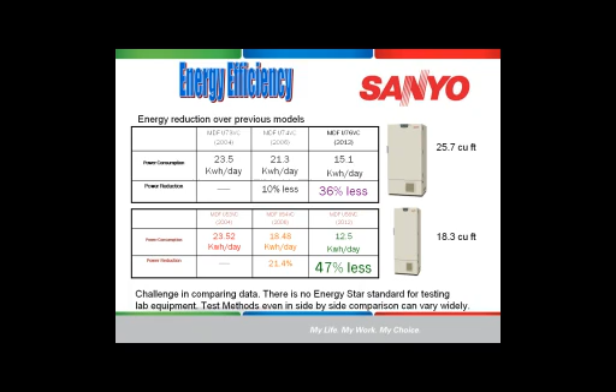Next issue and next thing that customers are looking for, because very often freezers are now stored in customer lab spaces where in the past that wasn't the case. So footprint has become a very important issue for high density storage, is what a lot of us are calling it now, as in how much space does a freezer take up in the room. Most manufacturers are moving toward vacuum insulation panels on the walls. In the past, the average ultra-low freezer, and still the conventional designs of ultra-low freezers, use 5-inch walls. You need 5 inches of blown insulation to be able to get enough R factor to be able to give you enough performance on the freezer so that you wouldn't be using a lot of energy and still keep uniformity inside the chamber. VIP, vacuum insulation panels, allow for half the thickness in the walls, which allows for a larger chamber, more box capacity for the same freezer size.